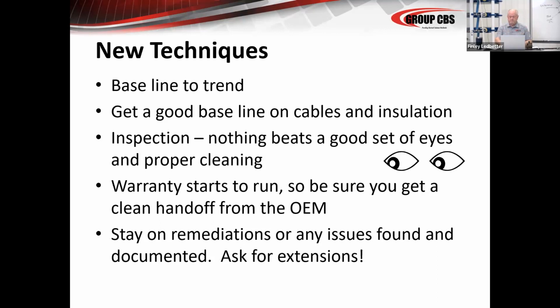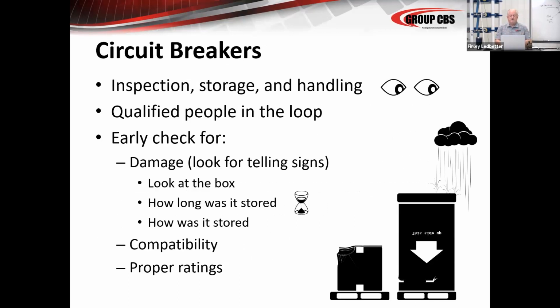Like we said earlier, inspection, storage, and handling, particularly of the circuit breakers, they come in boxes, crates like you see here at the bottom. What happens there quite often, the switchgear is shipped, sometimes goes directly to the pad. Sometimes the switchgear is shipped and goes into a storage building. Then that switchgear may get installed on the pad months, I've even seen years, before the breakers come out of the warehouse and get installed in the switchgear.